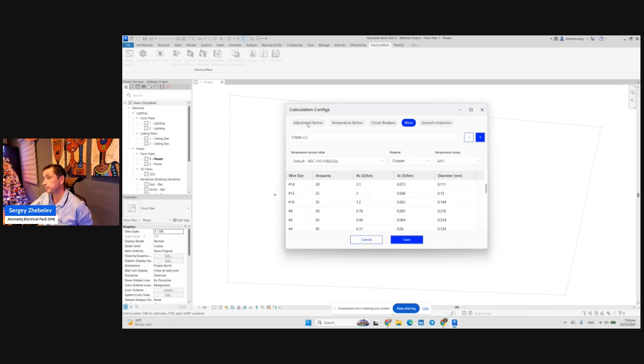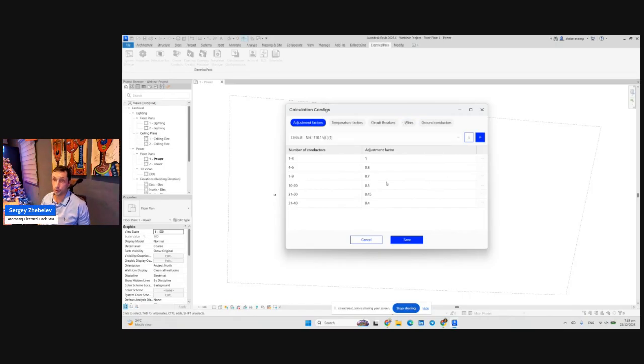Adjustment factors: as you know, when many current-carrying conductors are linked one to another in cable tray, conduit, or different conditions like soil, air, ground, they have different adjustment factors. If there are 5 wires in parallel versus 20 wires in parallel, the final wire ampacity will be different. So here we again have a default, but you can duplicate it and create your own by changing all the numbers here.